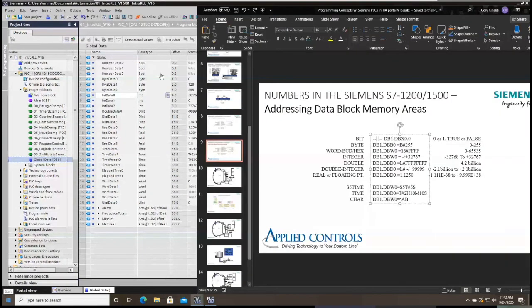Now that this is not optimized, it has a structure to it. So if we wanted to address Boolean data 0, we would do so using this notation. In this case, we're using data block 6, so it would be db6 dot dbx0 bit 0, because that correlates to byte 0 bit 0 here.